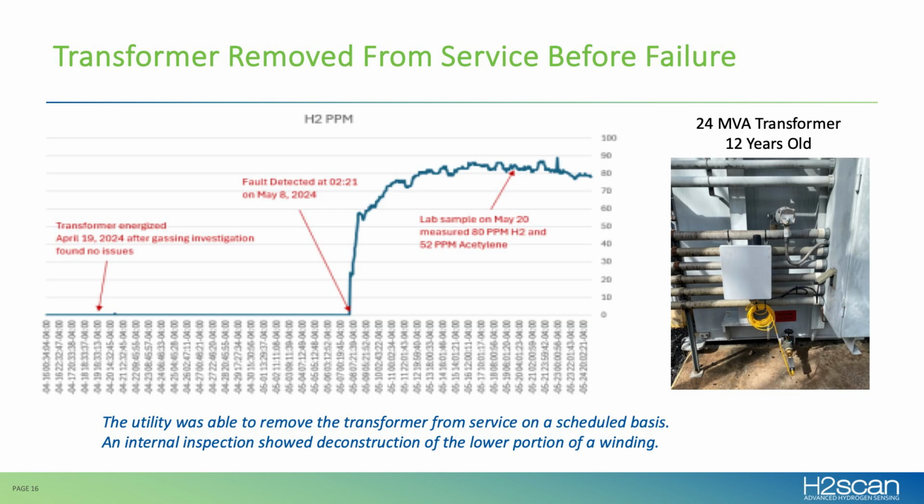Okay, so the next case, this again is very recent information. This is a 24 MVA transformer, 12 years old. I'm not sure if there were design issues. We don't know a lot about the history of this transformer, its operation, but there had been a close-in through fault, we know, right around the time the sensor was installed.